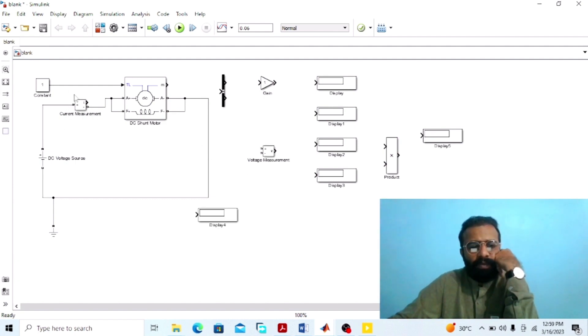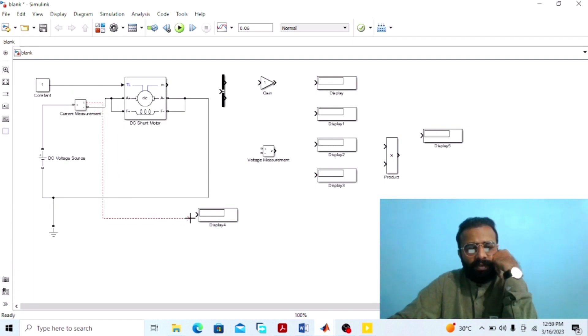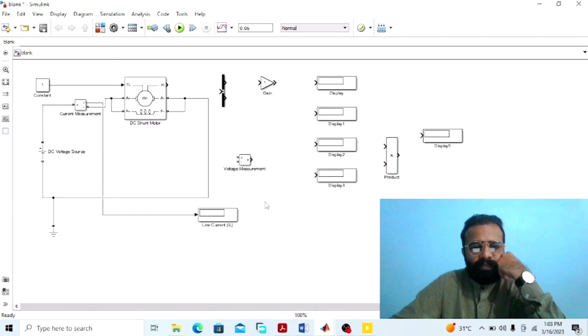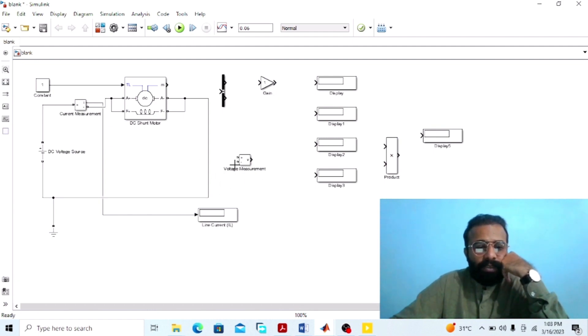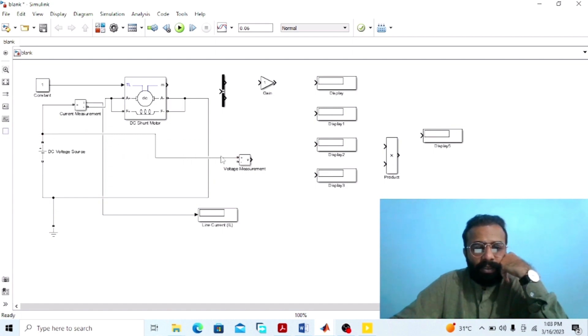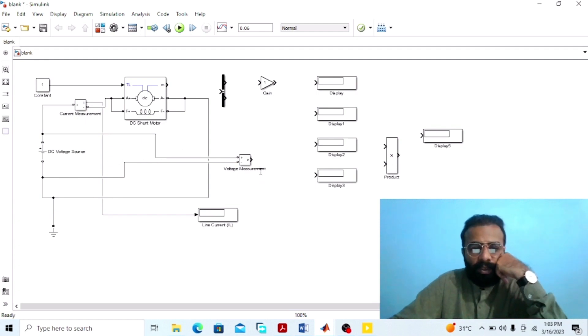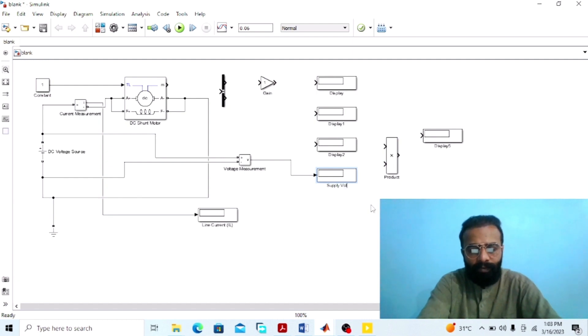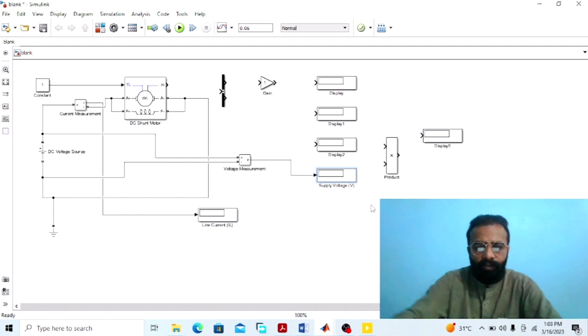This ammeter will give us the value of the line current in the case of the DC shunt wound motor. Connect this ammeter with the display — this display will give us the value of the line current IL. To measure the supply voltage, connect the voltmeter in parallel with the supply voltage. This voltmeter will give us the value of the supply voltage. Connect this voltmeter with the display, and this display will give us the value of the supply voltage in volts.